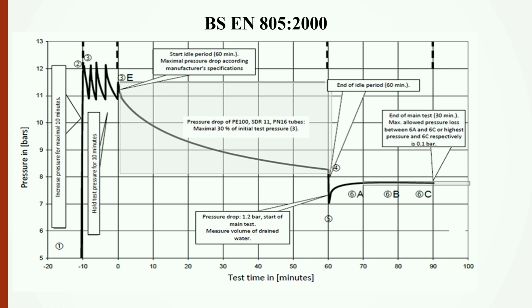Right, that's what the pressure drop test looks like in British and European standard 805-2000. What you do initially is you have a pressurization phase. This goes up to 12 bar, which I'll translate into American as 176 psi. It doesn't have to be 12 bar, that's set by the designer, but that's the sort of pressure we're talking about. So you raise the pressure to the test pressure. At that point, the pipe expands, which reduces the pressure, so your pump carries on for a 10-minute period and maintains that pressure at 12 bar.